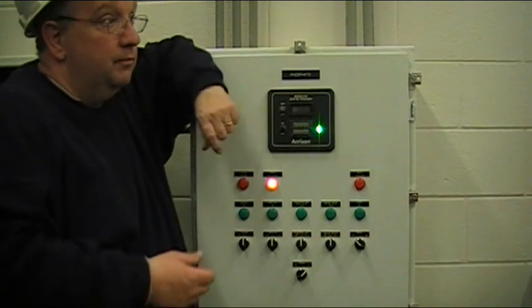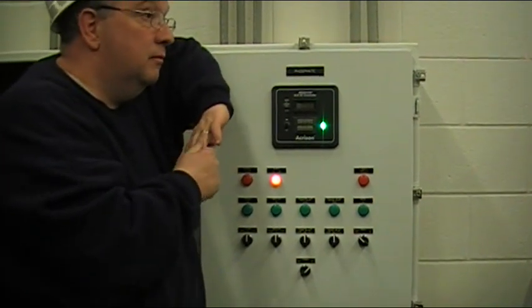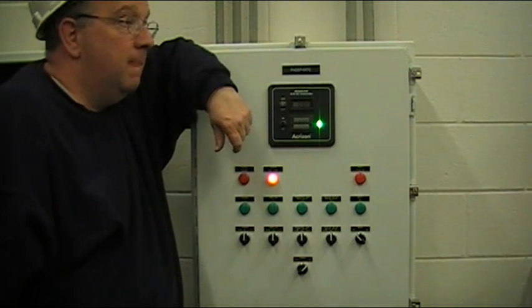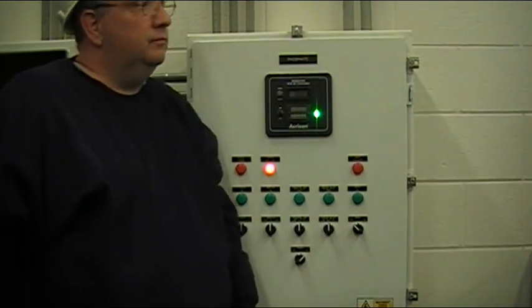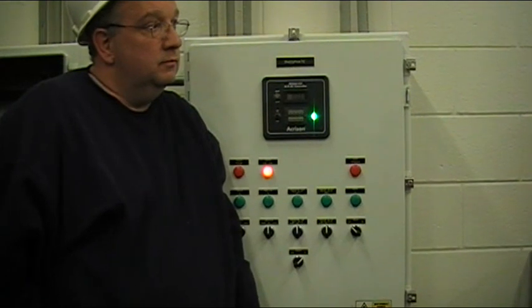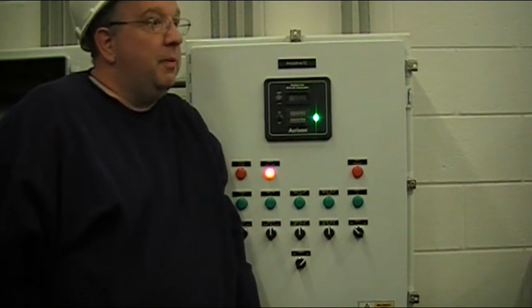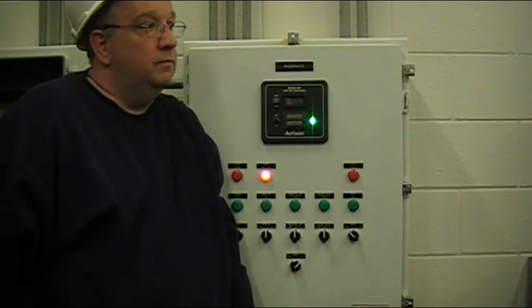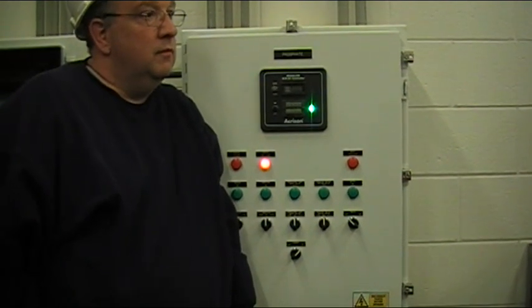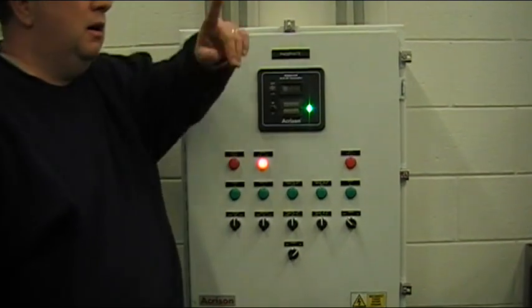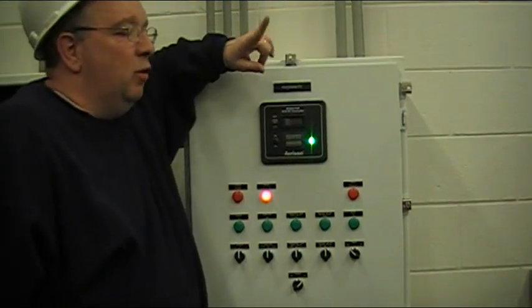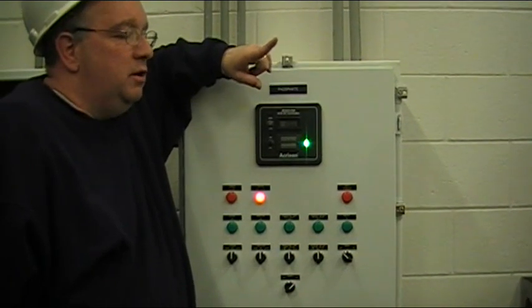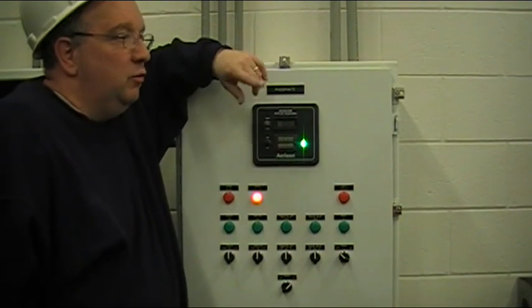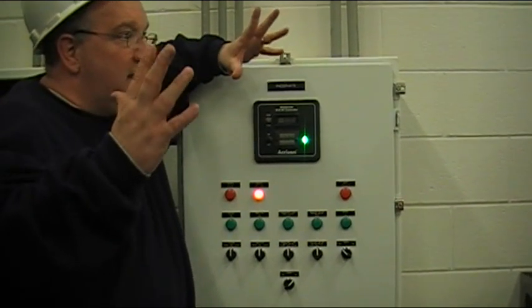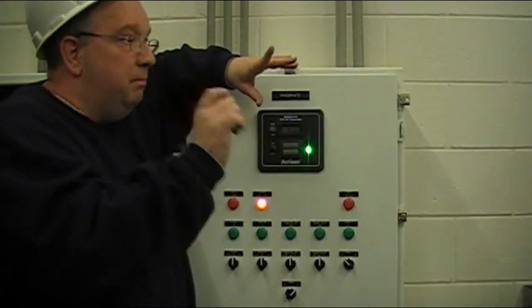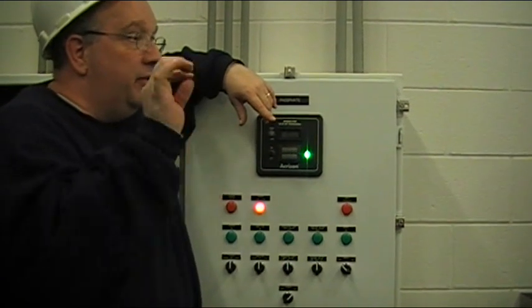So I have a question on that. Right now, this PRV over here that controls the water supply, which is also this water supply, hasn't been set yet. If that gets adjusted, is that going to adjust this? It's a possibility. What's the design operating pressure of this system? Each one is a little different, but the permanganate system is 114, the fluoride is like 130, and this one is like 115 to 120. On the drawings I gave you, one of the notes, in bold, tells you the minimum operating water pressure.